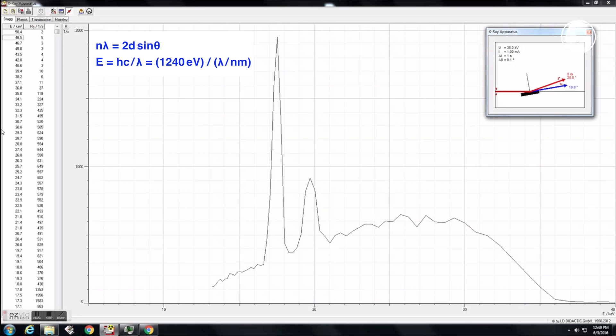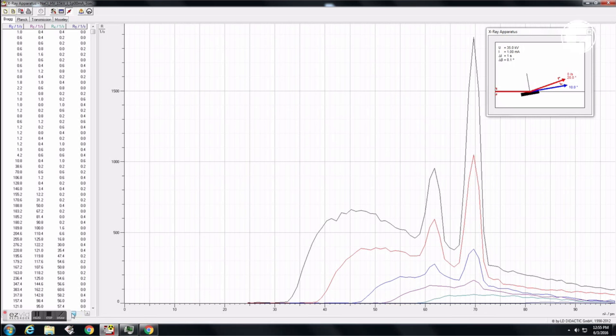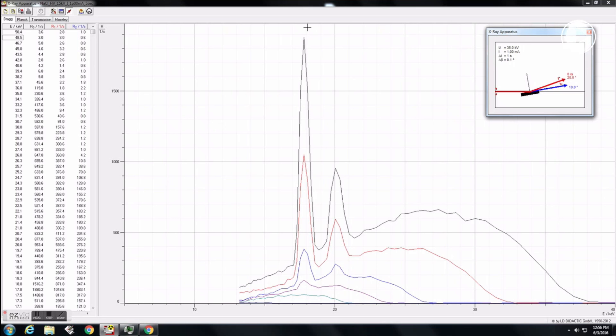And don't forget to save your data at the end. Now increase the acquisition time per data point to 5 seconds, and take data for tube voltages of 35, 30, 25, 22.5, 20, and 15 kV. Remember to save data to a file for each setup. The graph here shows the overlay of spectra for all 6 voltage setups.